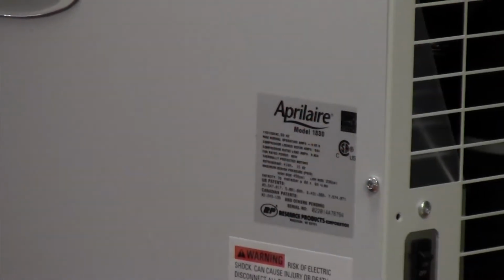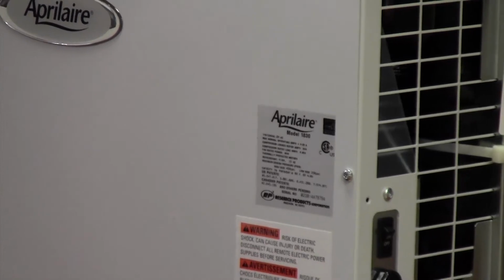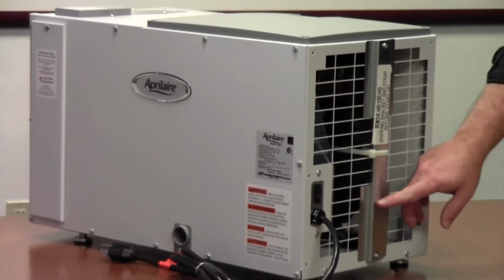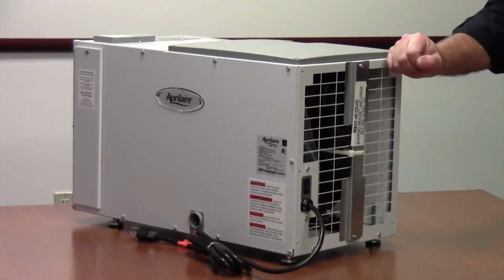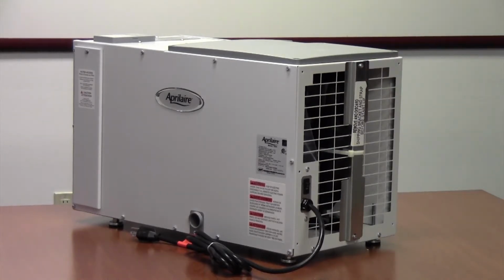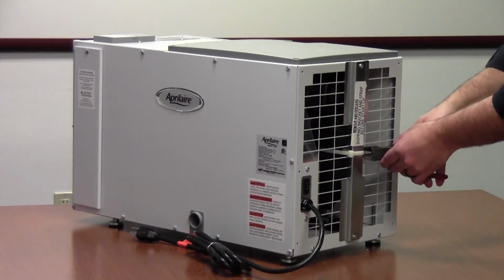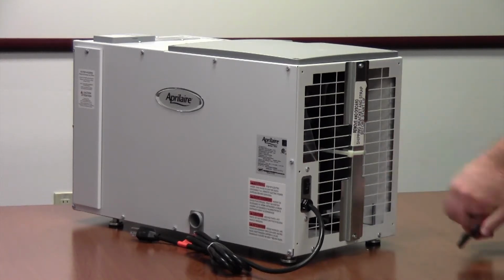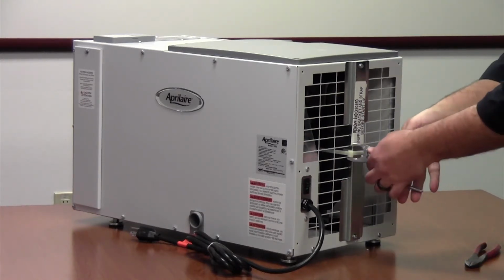Now we're going to go over the installation of this product, and one of the things that you'll notice is we ship this unit with a shipping retainer around the compressor to keep the compressor nice and tight and doesn't allow a lot of movement during shipment. So we're going to remove this strap that's on here. And you may need a pair of pliers to pull it off of there.